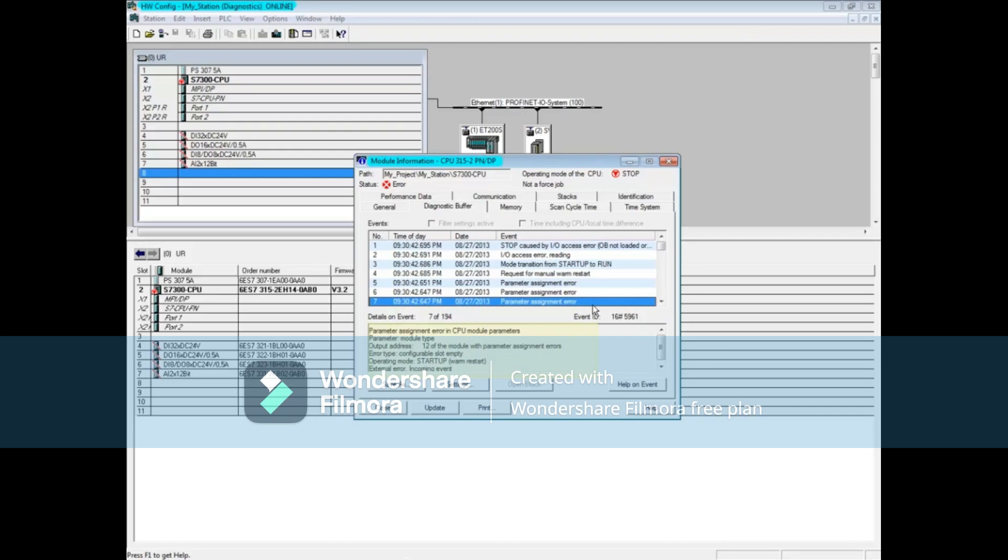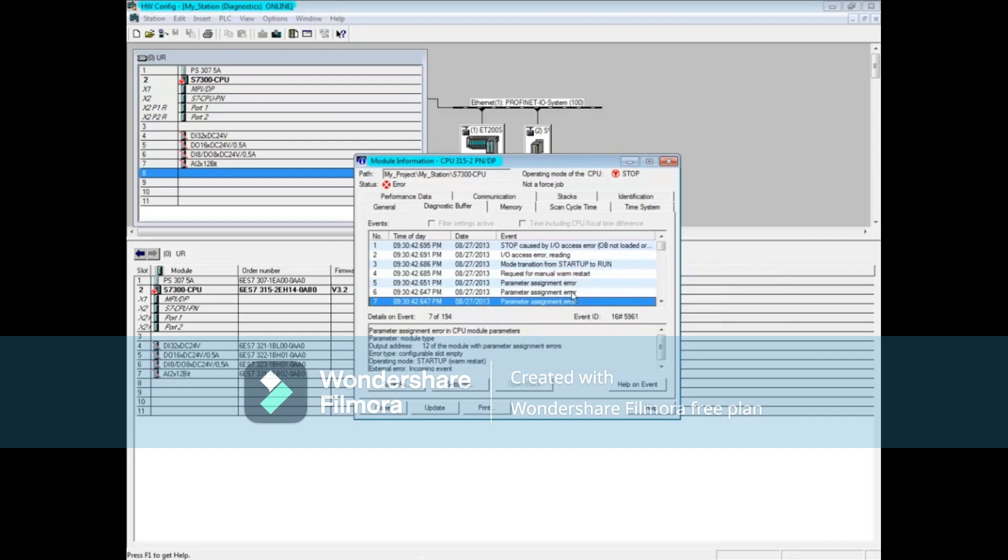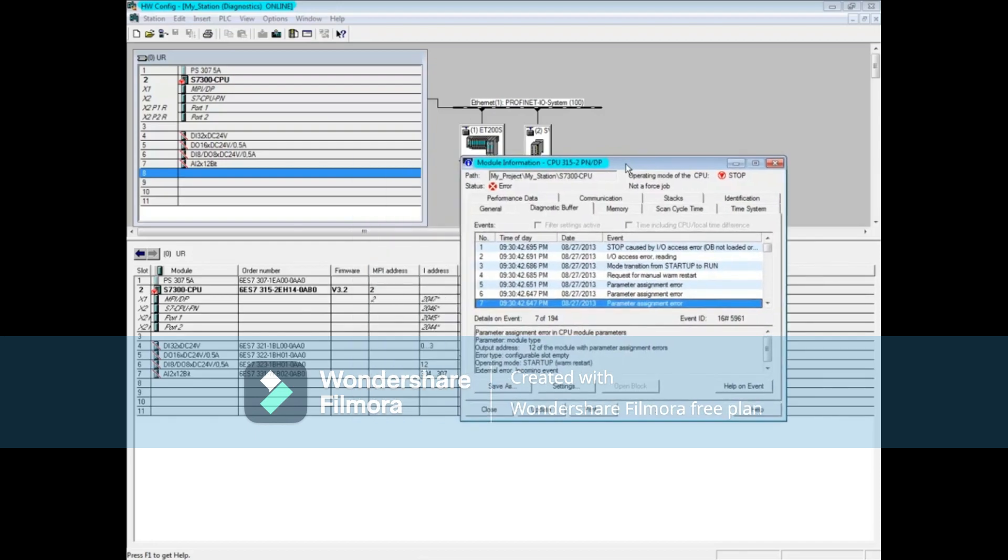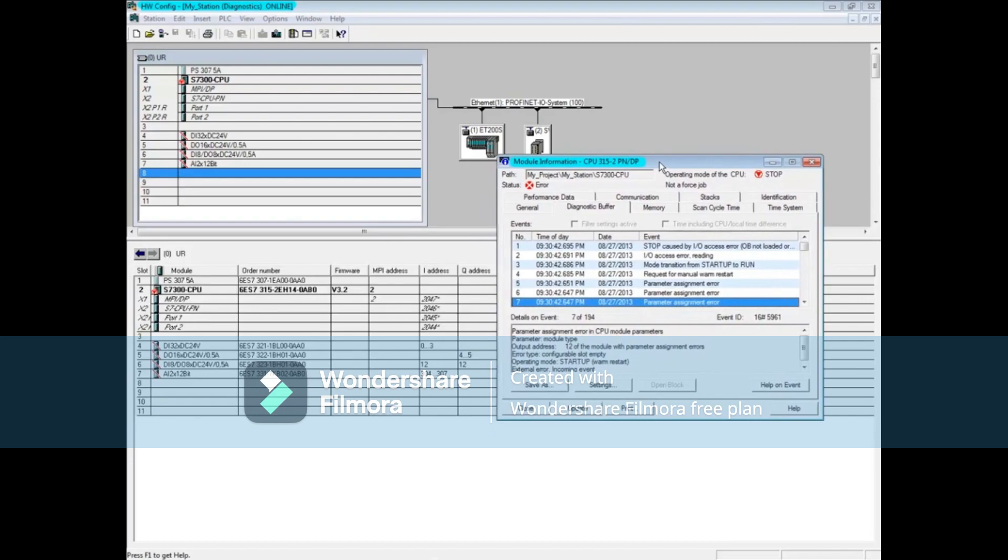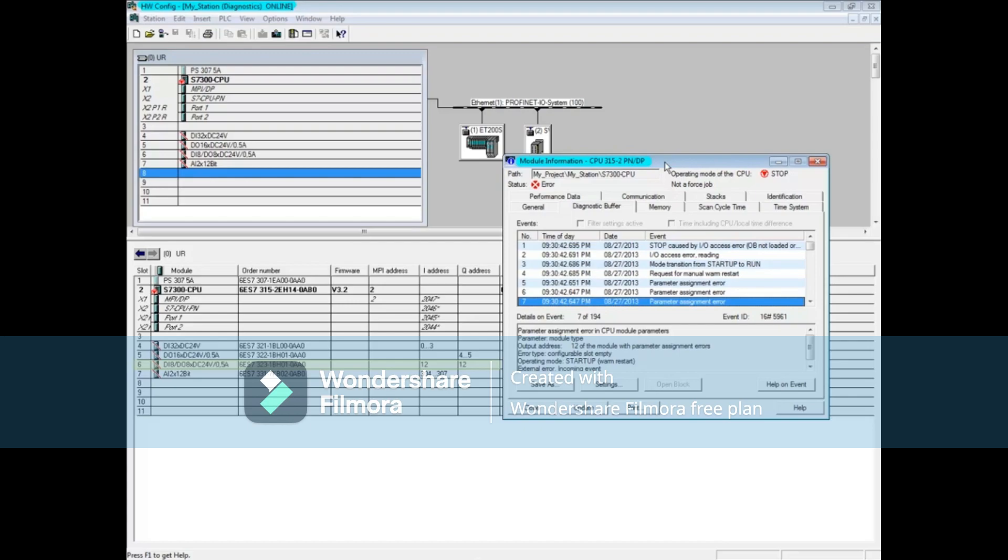Let's move the module information window to the right so we can see the addresses of the modules. Address 304 and 306 are from the analog input module in slot 7. Output address 12 is from the digital input digital output module in slot 6.